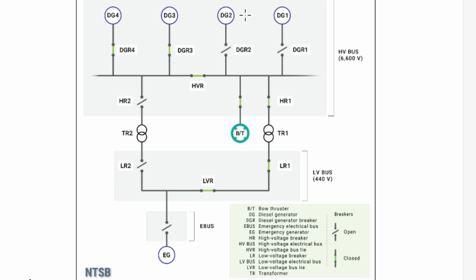So it automatically turned on diesel generator number 2, which had been sitting in standby priority, and now it was trying to supply power to the high power bus. About a minute later, before the power management system could get generator 2 up and running and fully synchronized, these two generators finally ran out of steam and shut down. Since it wasn't synchronized yet, you can't turn it on, so now you have no power to the entire ship.